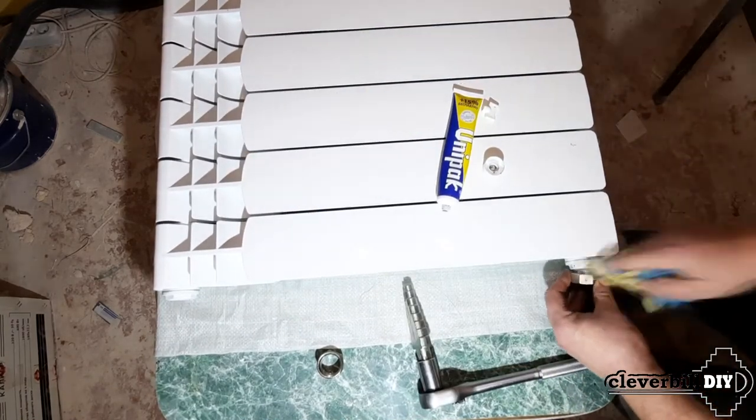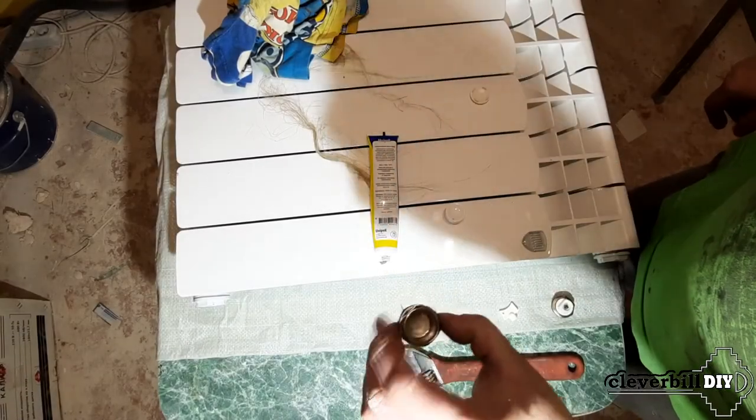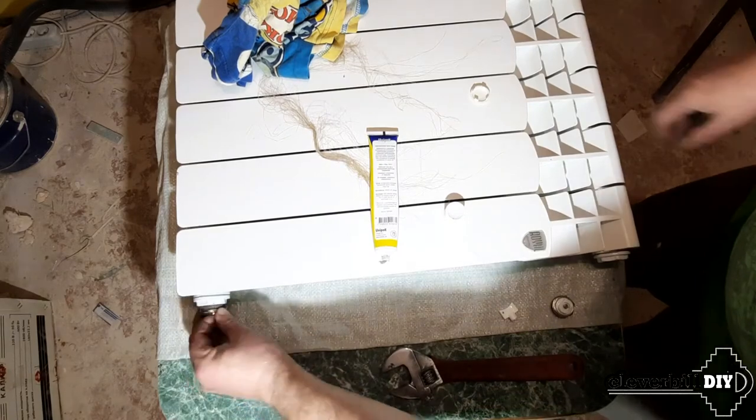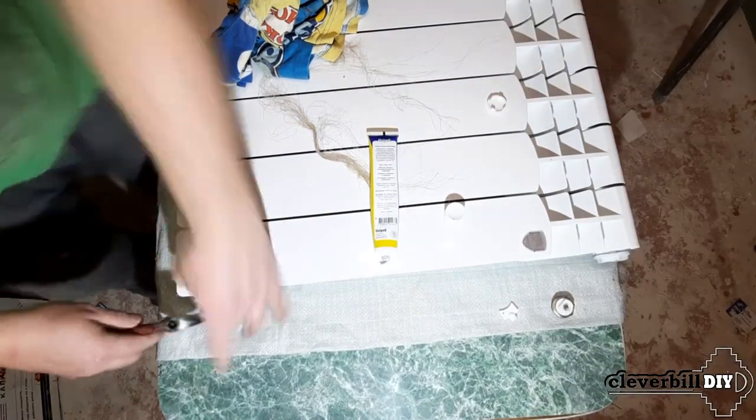I install the fittings on sanitary flax, screwing them into the connector using a stepped key connected to a ratchet wrench. On the other side of the radiator, I install a plug in the lower connector and a Mayevsky tap on the upper one.